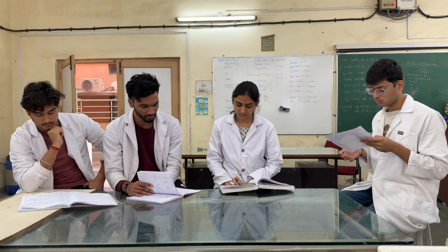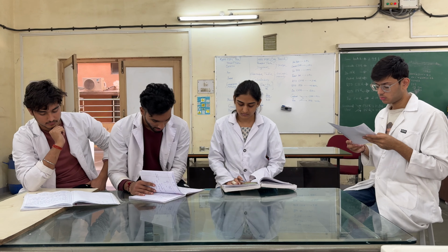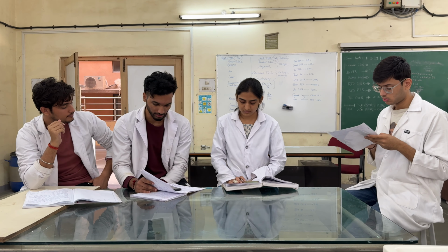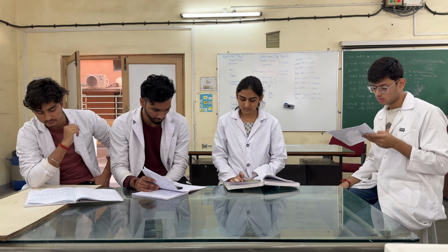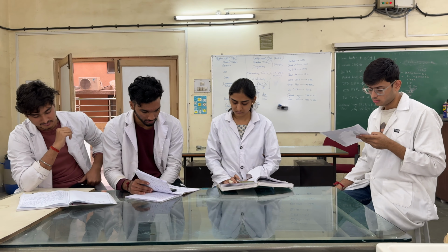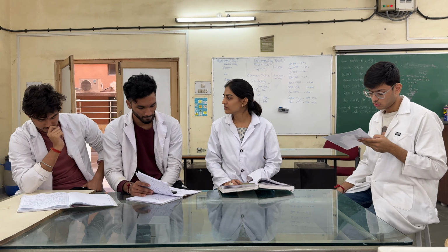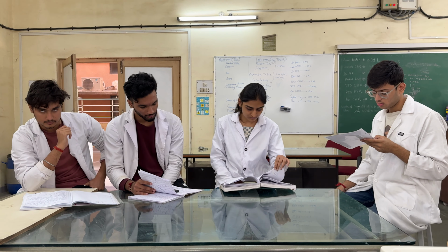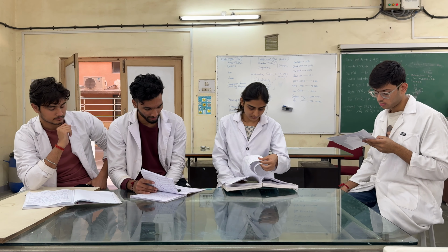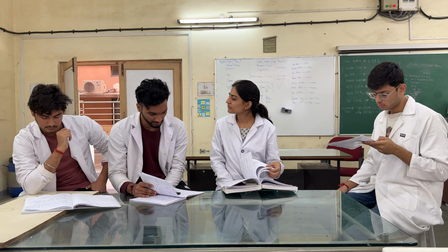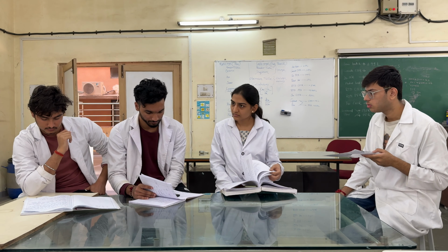However, deviation from the shape can reveal inefficiency. And what kind of inefficiencies might show? Good question. If the curve skews to one side, it could suggest channeling, where parts of the fluid are bypassing the mixing zone and exiting too quickly. If the curve has multiple peaks or an irregular shape, it might indicate dead zones.